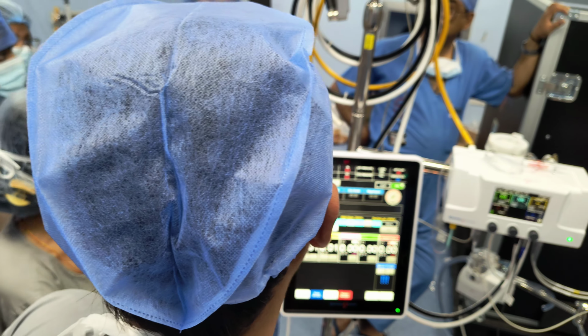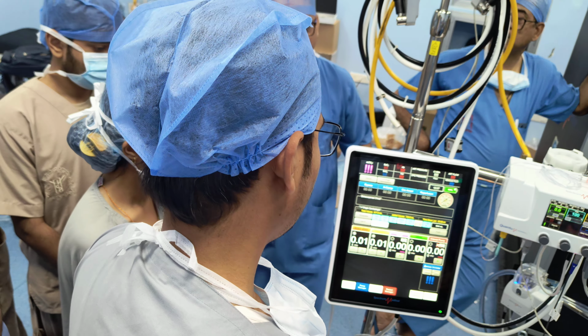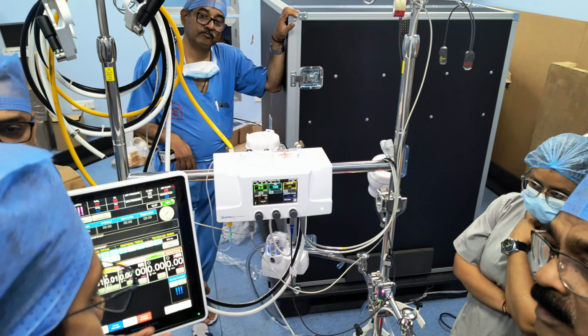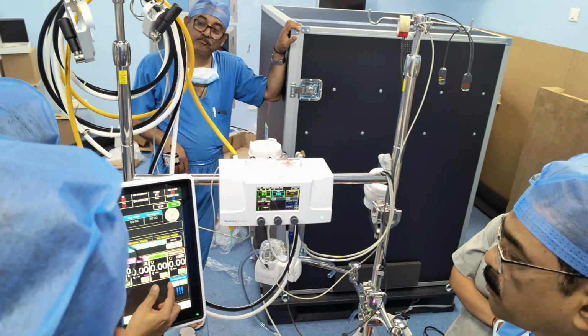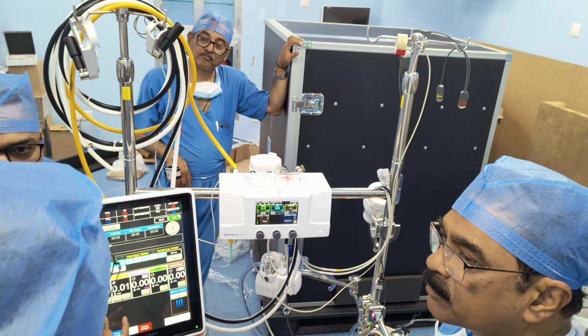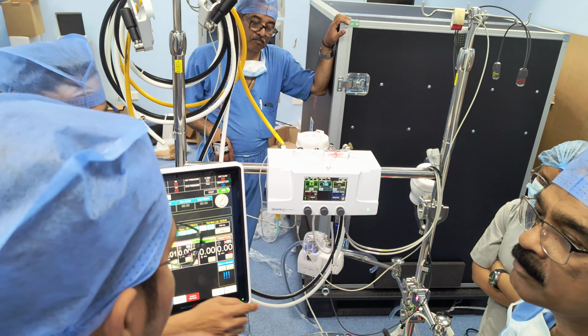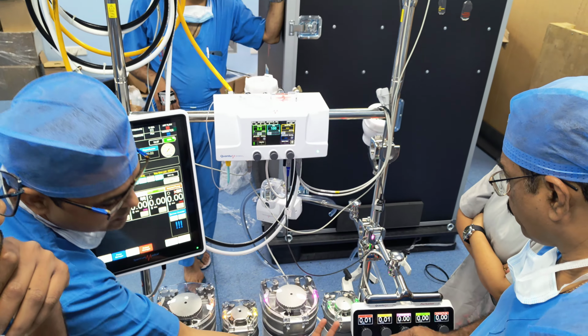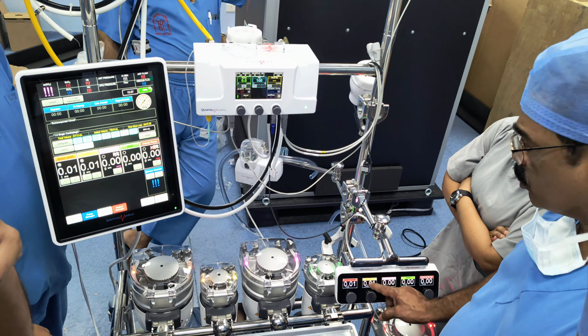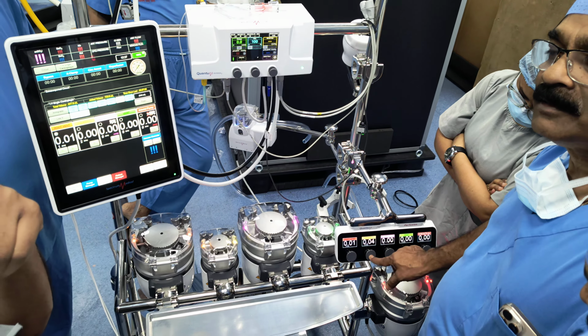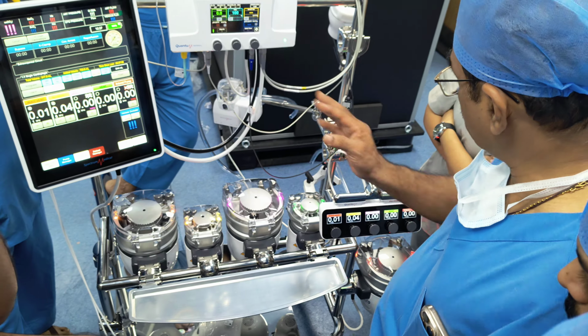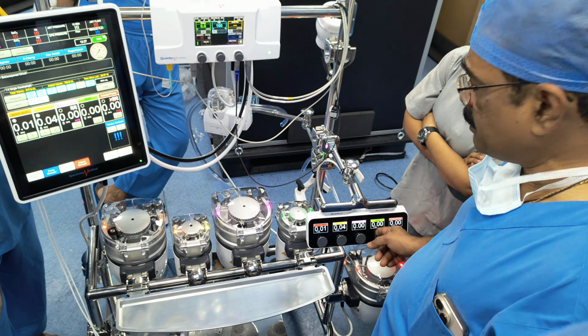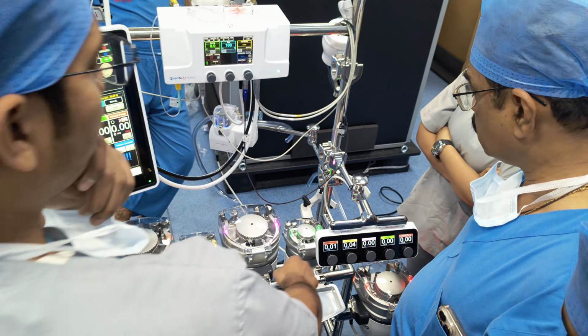No, in that case, Sandeep brother, you will lose one controller for your pump. Right now, all 5 pumps you control from your knobs. Can't we get an extra one? You can use this. They have given this toggling option so that if you get extra pumps here tomorrow, you don't need another controller like this. You just need to toggle it once, click and change to the other. So suppose I can control 2 suckers with this knob. Okay. If you want the venous occluder as a separate knob, then I have to, no, can we have an extra one for venous?